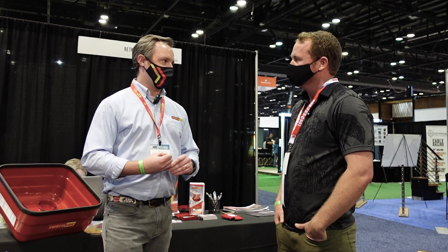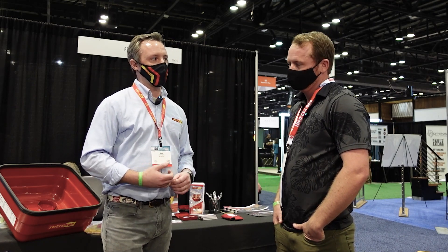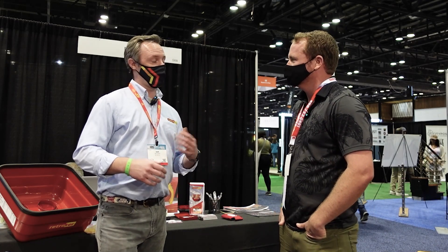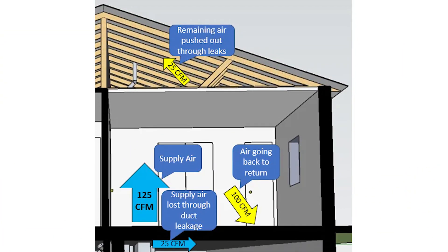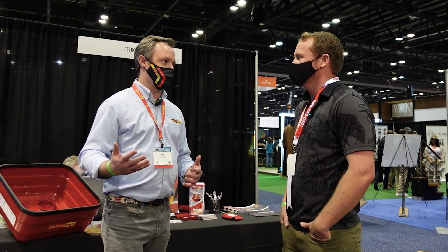It's hard to say the building envelope is not a part of the HVAC system. Depending on how leaky certain ducts are — whether it's on the supply or return side — the system is going to push and pull on certain parts of that building envelope. Say we have a bedroom that's getting more air than it should. We shut the bedroom door and it's getting overpressurized. And if that air doesn't have a way to get back to the return, that room is going to overpressurize, and if it's leaky, it's going to push that conditioned air outside of the envelope — amplifying the leakage.